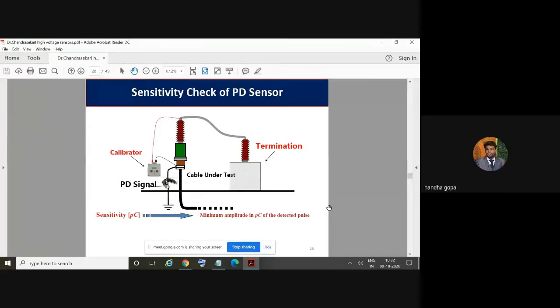Okay. So now the real challenge for a test engineer or the persons going for monitoring these types of activities is to understand whether we are really measuring the PD signal or leakage current signal, what is happening inside the equipment, or whether we are measuring some unknown signals from outside. So it's very, very tough actually.